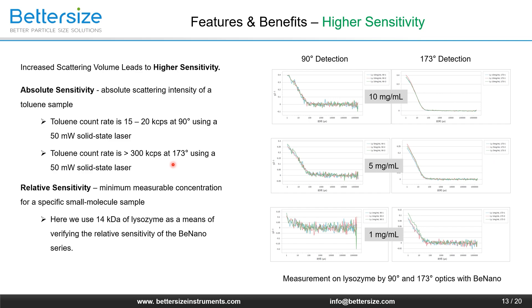Another sensitivity is relative sensitivity, defined as the minimum measurable concentration for a specific small molecule sample. Here we use lysozyme, a very common protein with molecular weight of 14 kilodaltons, to verify the relative sensitivity of the backscatter optics. When lysozyme is measured across a range of concentrations, the backscatter detection gets much higher quality correlation functions as compared to 90-degree detection. Therefore, the superior relative sensitivity of the DLS backscattering technology has been verified.